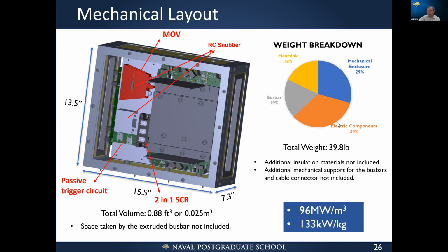As you can see, the electric components, mainly the modules, are about one third of the weight. The majority of the weight still comes from the mechanical enclosure, the heat sink, and the bus bar. We may need to add additional insulation materials later to meet the insulation requirement. This has not been included, and we may need additional mechanical support for the bus bars, which so far has not been included either. With these designs, the power density is about 96 megawatts per cubic meter, or 133 kilowatts per kilogram. So with this, I think we still have some margin to meet the 100 kilowatt per kilogram target.